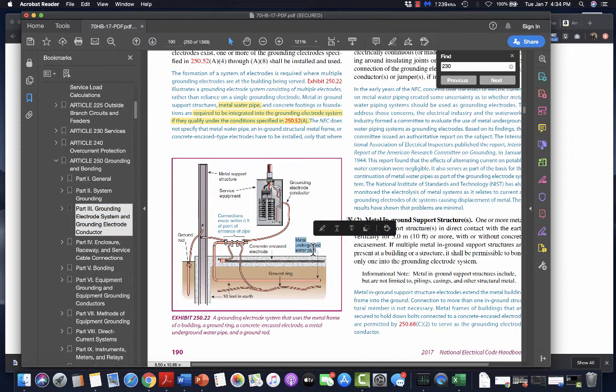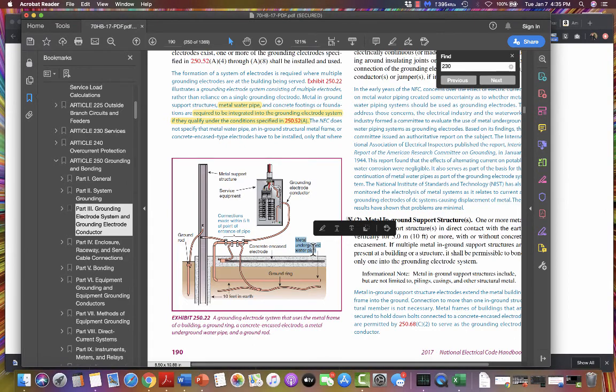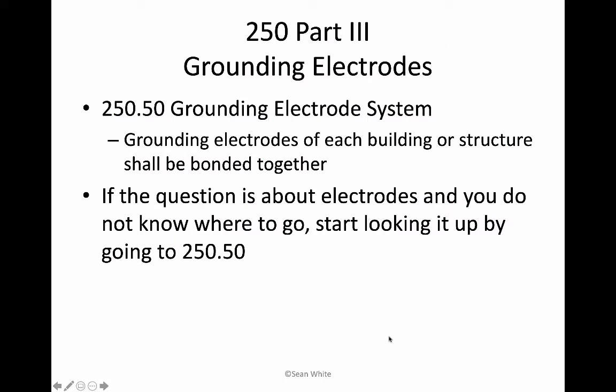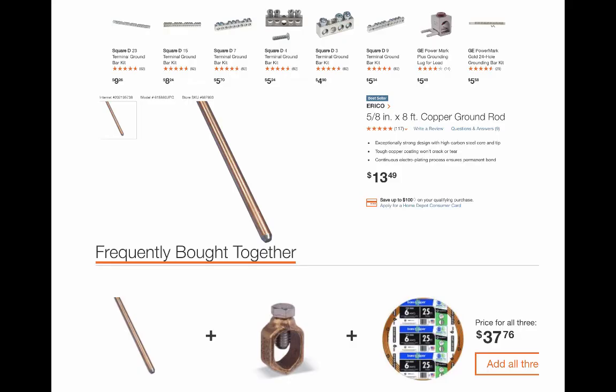But you know what kind of pipe you can't do? One that's filled with explosive gas, fossil fuels. Not for the solar people. So if you don't know where to go when they say electrode and you're on a test or you're just in the field and you've got some NEC books, go to 250.50, 250.50, 250.50. Repetition is good for things.